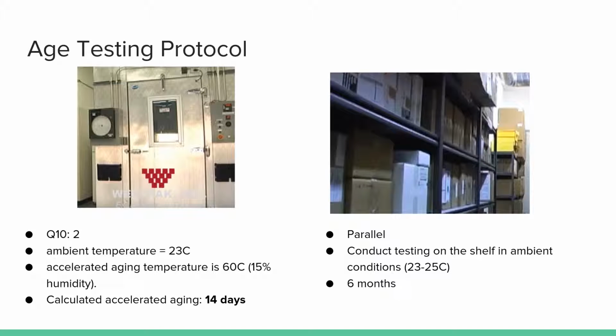To validate that our product can sustain a shelf life of 6 months, we conducted age testing at Westpak because we knew they could accommodate our selected parameters and sample sizes in their chambers. Based on the research of our materials and their data sheets, we decided 60 degrees Celsius aging temperature and 15% humidity were feasible and calculated a 14-day accelerated aging time was appropriate for our application. In parallel, we conducted a real-time aging test where we would set the packages on a shelf for 6 months in ambient conditions. In terms of acceptance criteria, we want to ensure the sterile barrier of the packaging was intact and that the device is still functional.